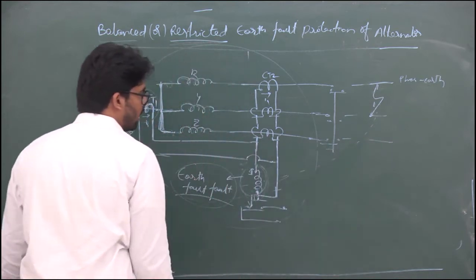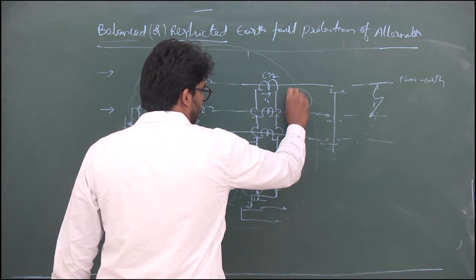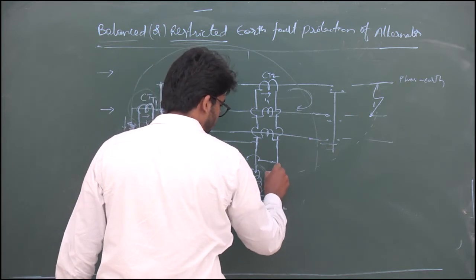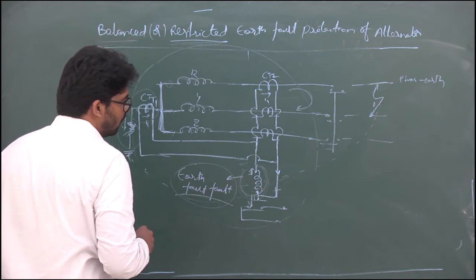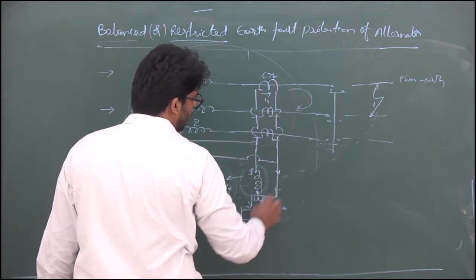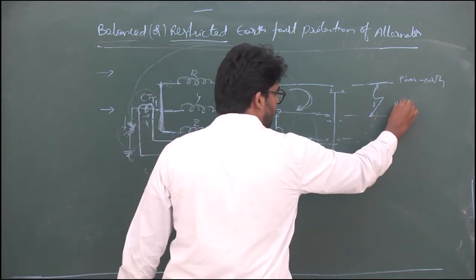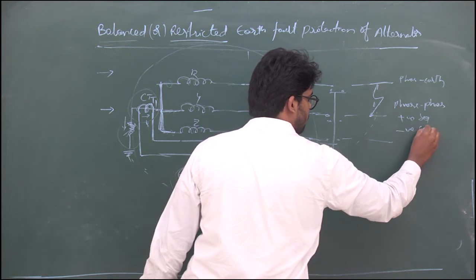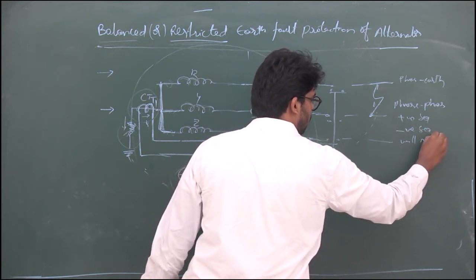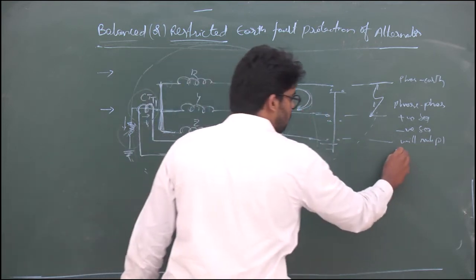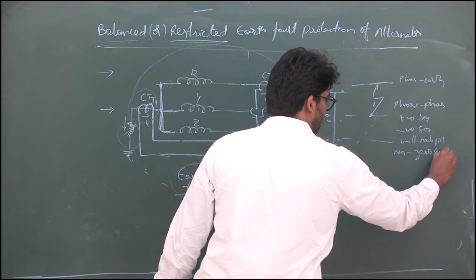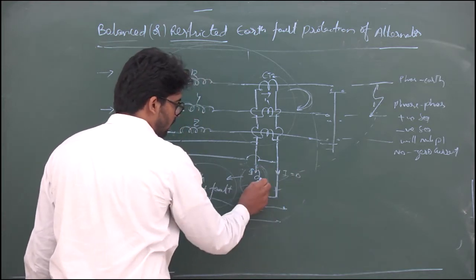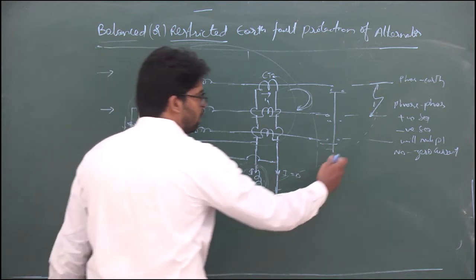Now, if a phase-to-phase fault accidentally occurs, the current is flowing in that loop only, so there is no possibility of current flowing through the relay coil. If we take the sum of currents for a phase-to-phase fault, all the positive sequence and the negative sequence components will get nullified due to circulation only. So there is no possibility of zero sequence current — zero current will not flow through the coil, therefore this coil will not operate for external faults.